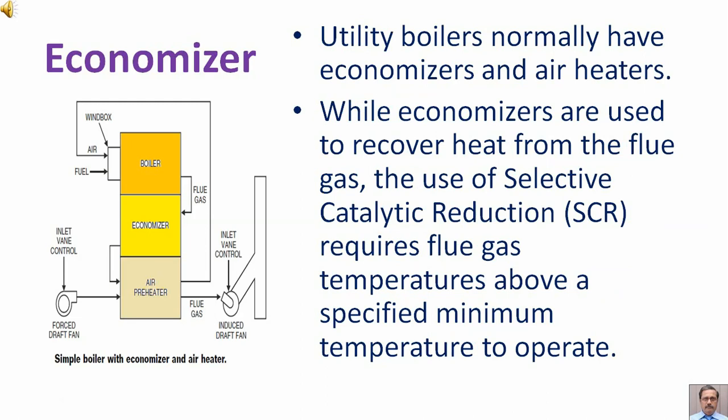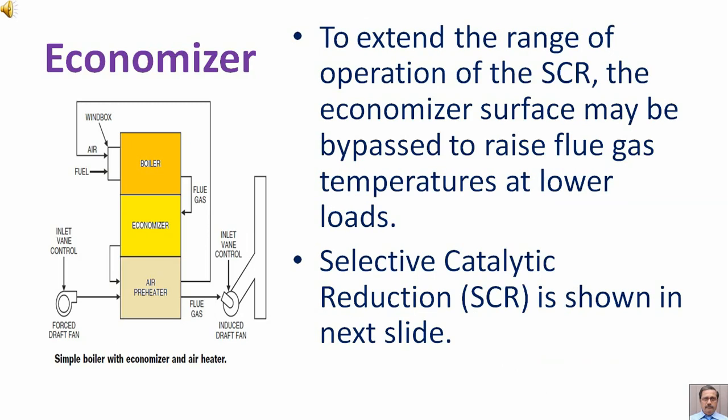While economizers are used to recover heat from the flue gas, the use of selective catalytic reduction (SCR) requires a flue gas temperature above a specified minimum temperature to operate. To extend the range of operation of the SCR, the economizer surface may be bypassed to raise flue gas temperature at lower loads. Selective catalytic reduction SCR is shown in the next slide.